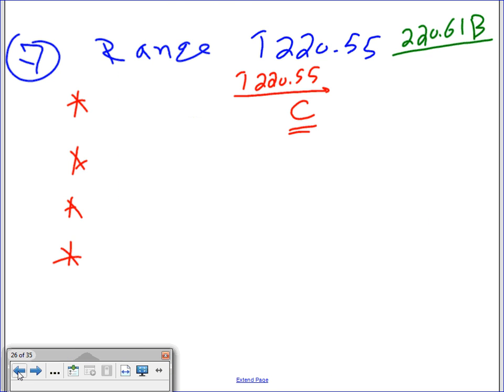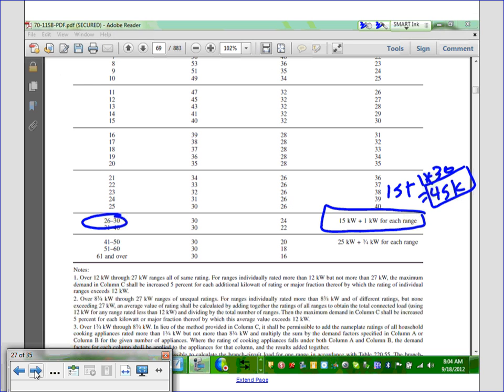Okay, so let's go to the ranges. For the ranges, guys, remember that table that talks about ranges? Here's the table. Do you guys remember the size of my range? The size of my range is 19 kW. And I have how many of them? I have 10. Here's my 10, and 19 will be 25. Can you guys see that? I have 10 ranges. They're all 19 under column C, so their demand is 25.